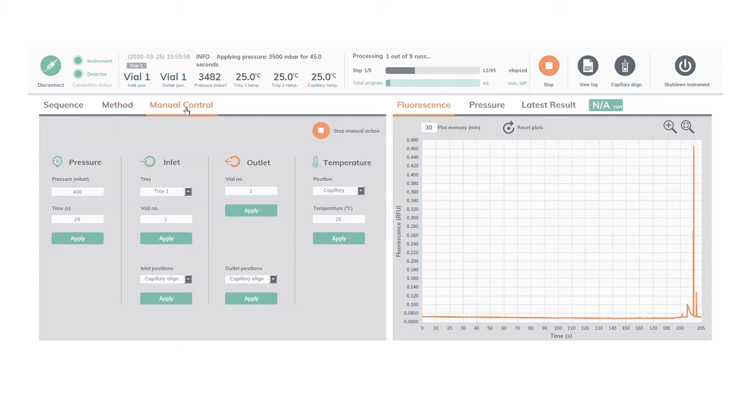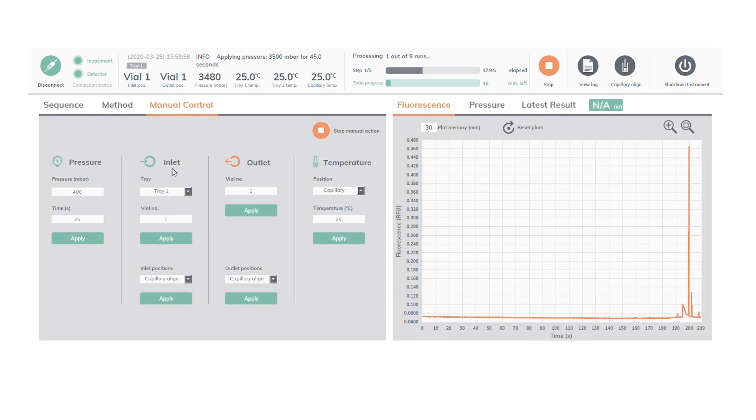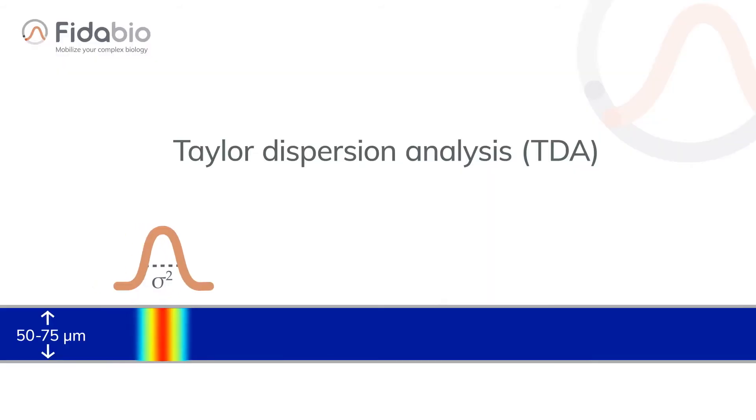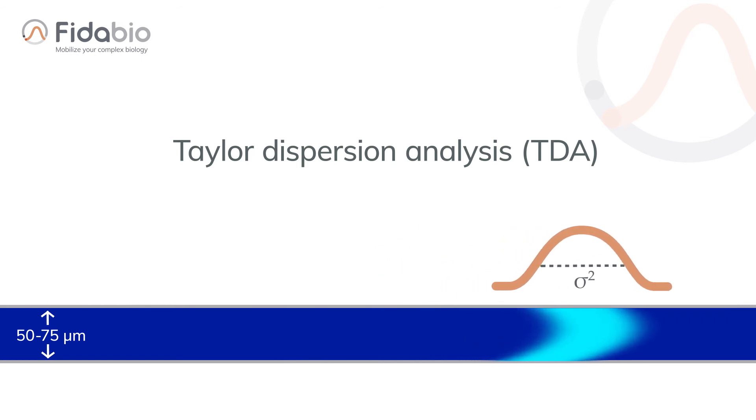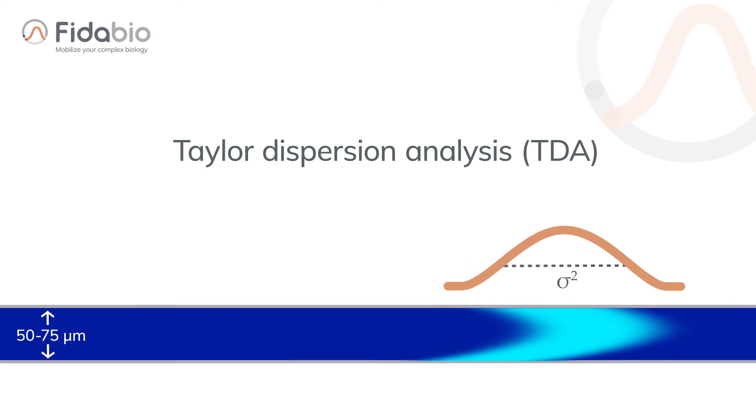The Fida principle is based on a pressure-driven flow in a microfluidic channel. The shape of the signal is determined both by the pressure that you apply to the channel, but also by the diffusivity of the system you are looking at. Small molecules diffuse fast, large molecules diffuse slow. We extract the diffusivity and convert it to a size. This is how the Fida principle works.